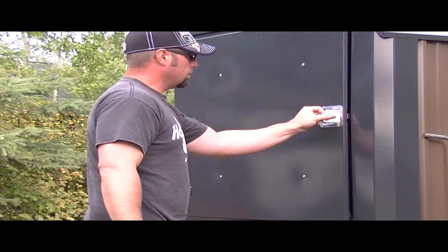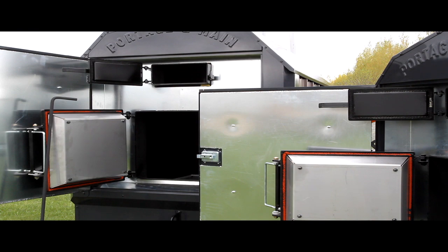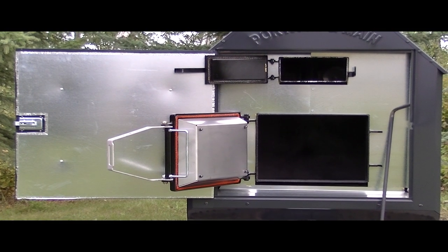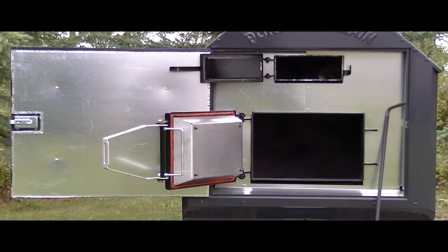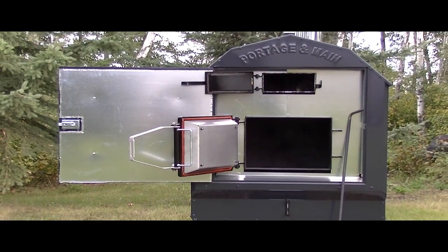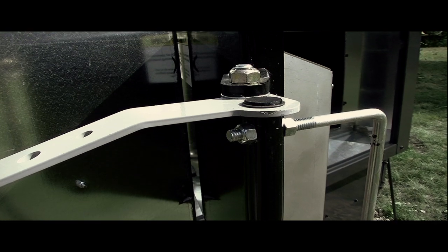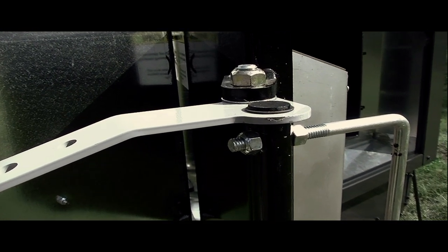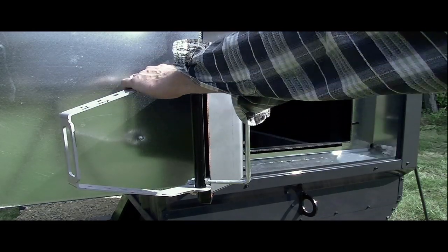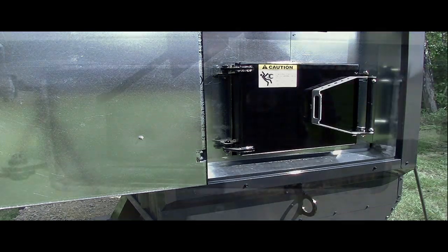Opening the main access panel of the BL series stove, you get a sense of how robust it is. This insulated outer door protects the interior door jams and sills from weather. It also helps keep these sensitive areas warm. Having them exposed to cold, moist air can lead to condensation and in turn the possibility of corrosion. Heavy duty locking mechanisms ensure doors and access panels are kept secure. By maintaining a tight seal on fire chamber and heat exchanger doors, the Ultimizer avoids air leaks that may lead to the formation of creosote and keeps any messy combustion byproducts inside the unit.